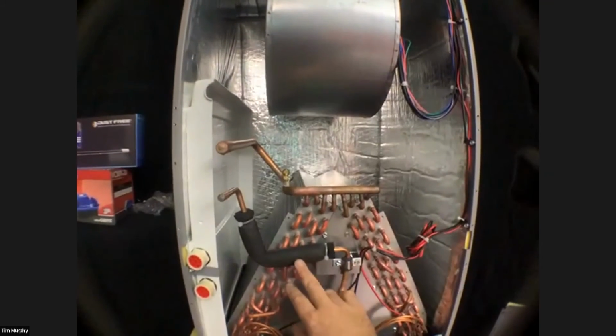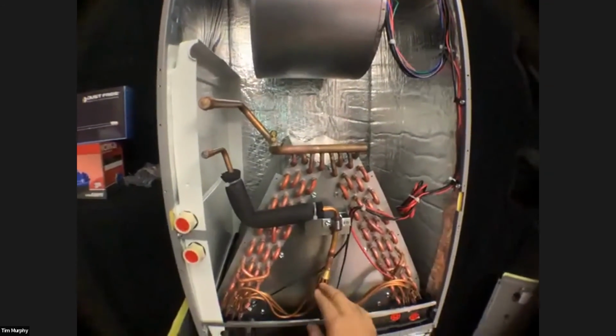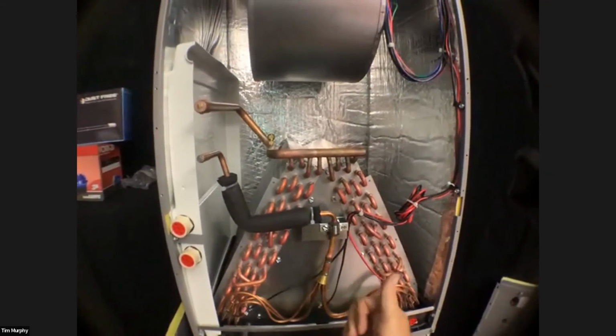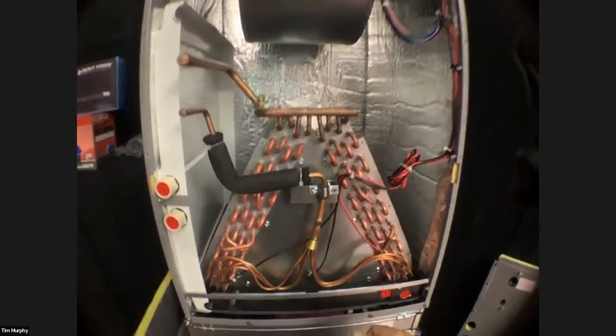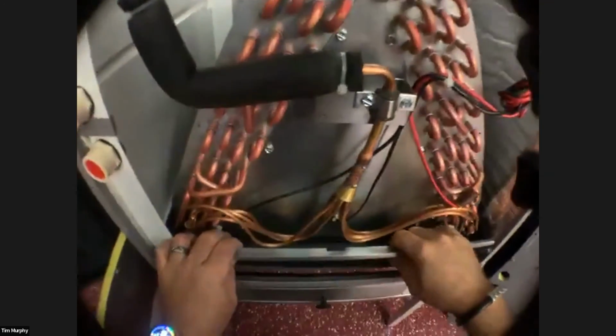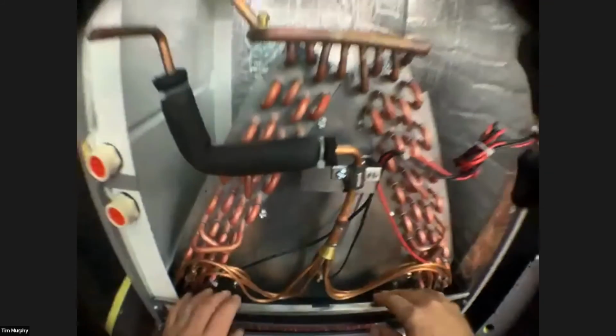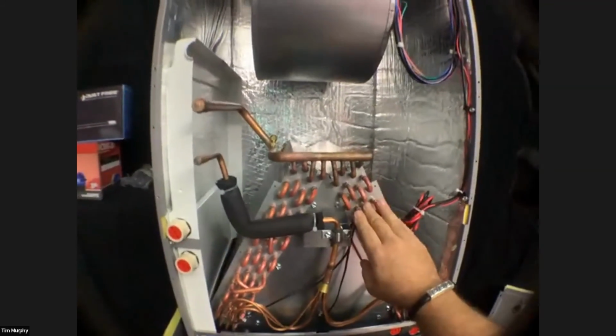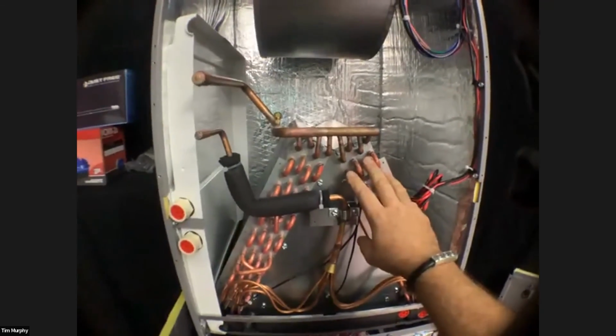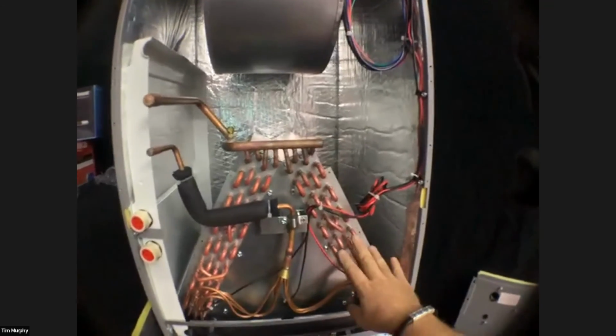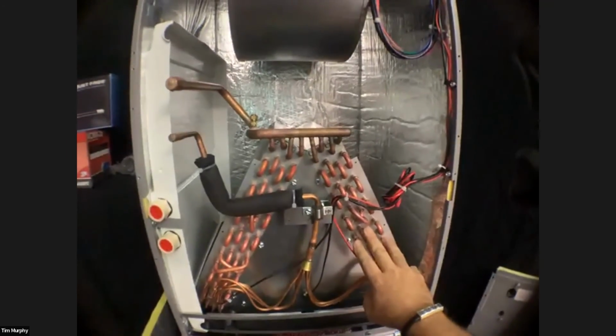But another thing, as I mentioned before, if you notice, there are no TXVs in this. The expansion valve is outside at the condenser. There's plenty of room to clean out the front of the drain pan. And this is a copper tube and fin coil. It's not a microchannel. So that makes life a lot easier when you need to clean the system.